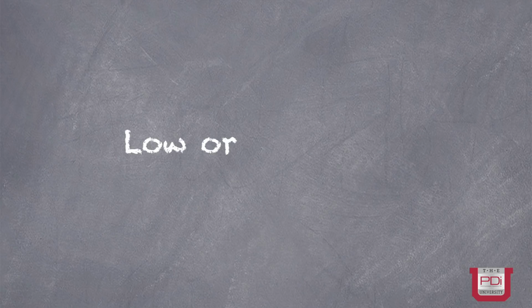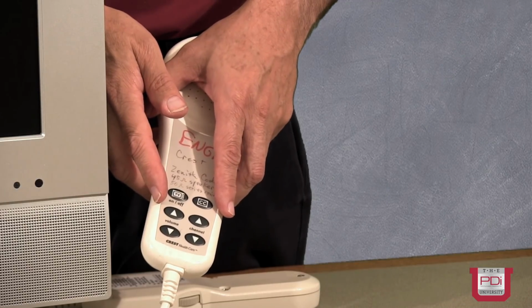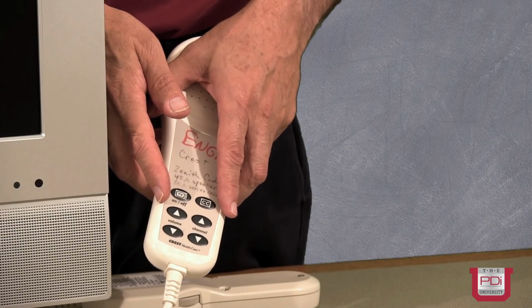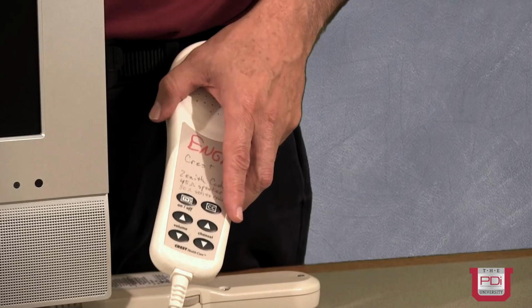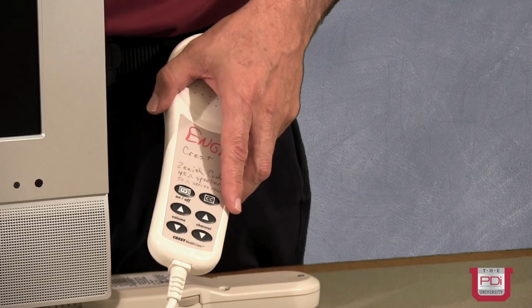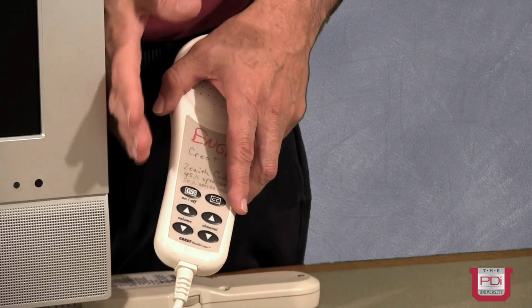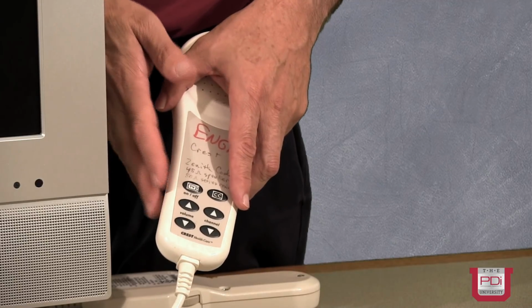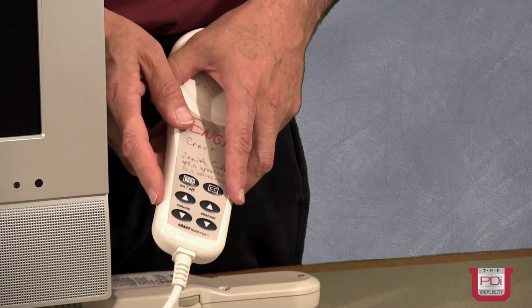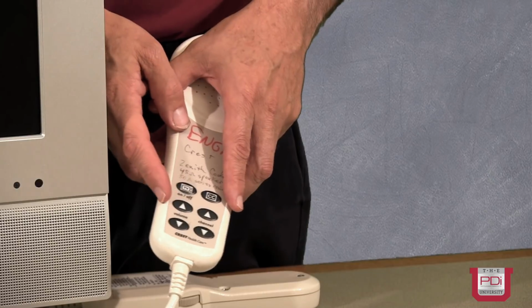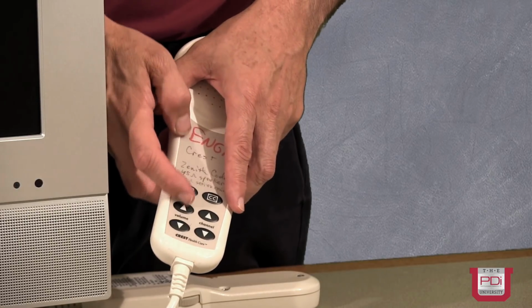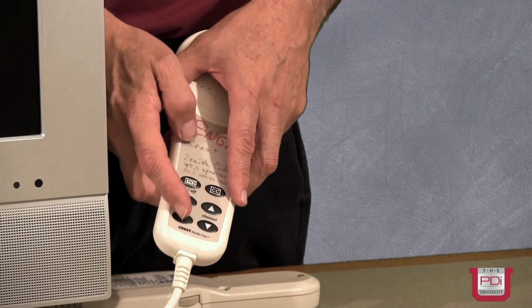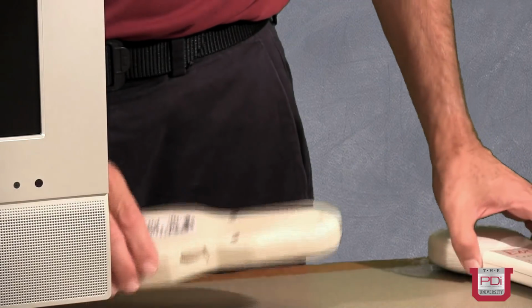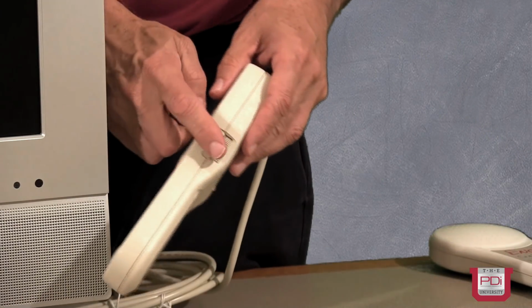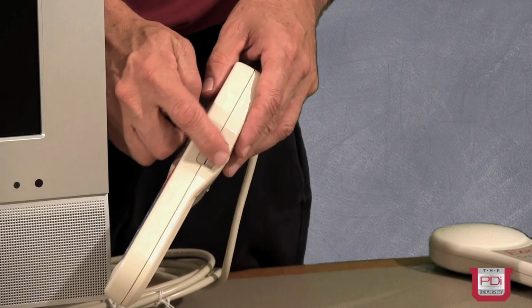One of the other common issues is low sound or missing sound to the pillow speaker. And there are basically two styles of pillow speakers. One of the more advanced styles actually has a dedicated volume up, volume down button. And pressing that volume up or volume down button is much akin to pressing the volume up, volume down button on a remote control. Another style is the one in which there is a side-mounted volume control.